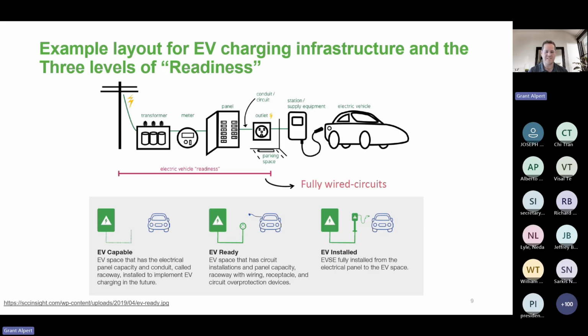The next level is EV ready, where the conduit, wiring, and a receptacle are installed, but there's no actual EV charger installed. That's called an EV ready parking space. There's circuit overprotection and the receptacle, but you still can't plug in an EV there. The 100% ready space is called EV installed. There's the panel, the wiring, the outlet, and the receptacle either has the supply equipment plugged in or the supply equipment is hardwired.